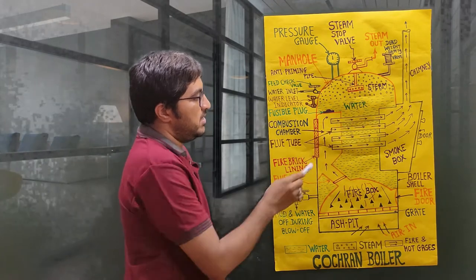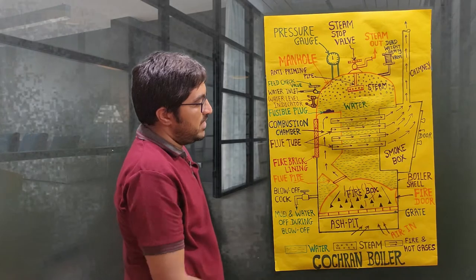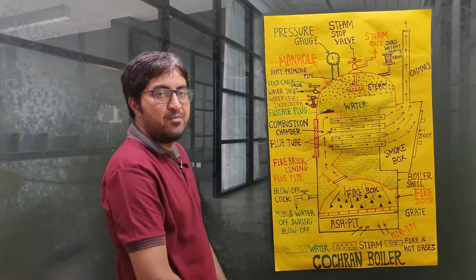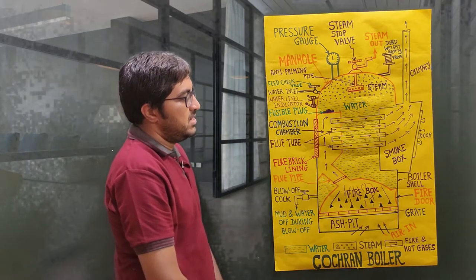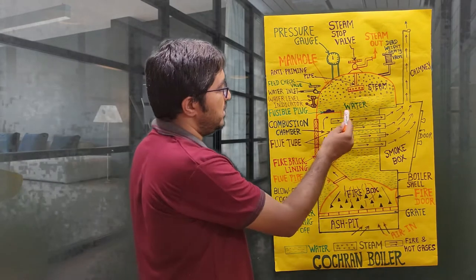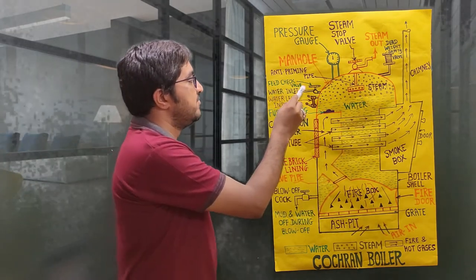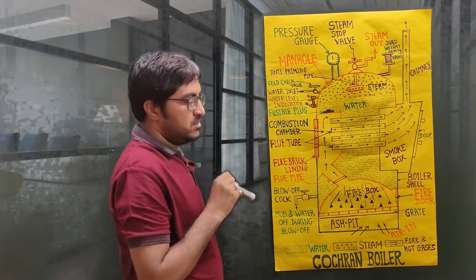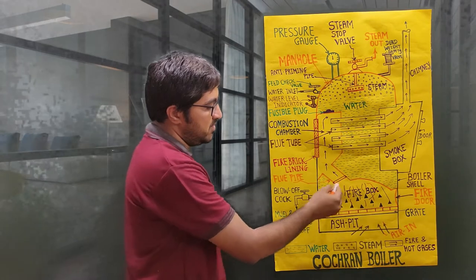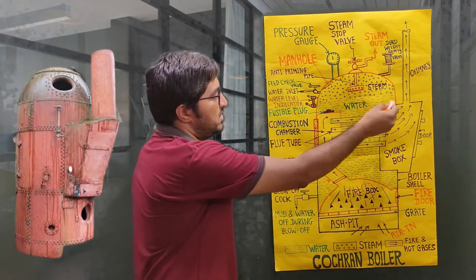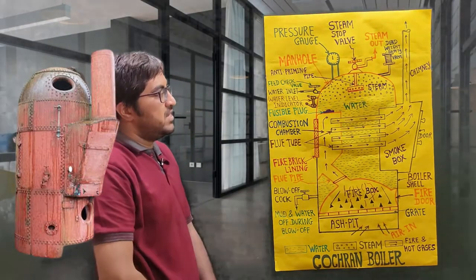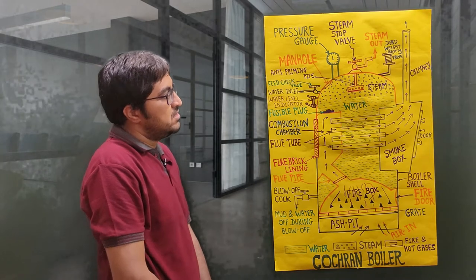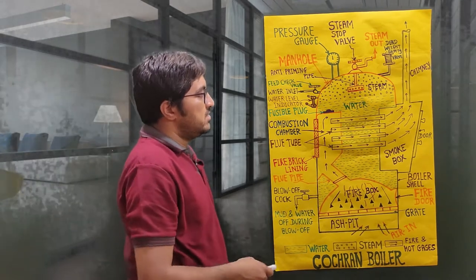The arrows show the direction of the hot gas flow. The hot gases pass through the inside of the tubes, which is why this is called an internally fired boiler. Since there are more than one tube, it is a multi-tubular boiler. Surrounding the tubes is water, filled through the feed check valve into the shell. A main feature of this boiler is that the firebox is hemispherical in shape, and the top of the shell is also hemispherical, providing better strength with less material in a compact size.